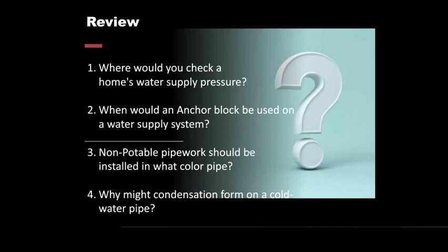If you've got a limiting valve on a system or a pressure reducing valve, the hose tap, usually the first hose tap by the garage or close to where the water comes in, is usually unlimited. So if that's a possible issue, you can tell, because you might test at the shower or something, find you've only got 100 kPa, but you test the hose tap outside and you've got 700 kPa. So you know that the limiting valve is either faulty or needs adjusting.